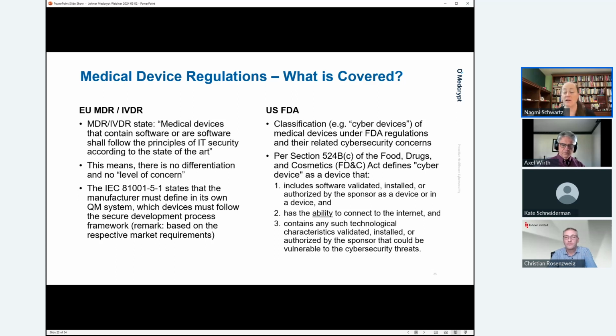You include software, you have the ability to connect to the internet, not necessarily the intention to do so, and you contain technology characteristics that are validated, installed, or authorized that could be vulnerable to a cybersecurity threat. Quite frankly, I perceive any software that's installed on a device to be potentially vulnerable, so I think 1 and 3 are a little bit redundant, but these are ANDed. A cyber device is only something for which all three of these characteristics are true. In the guidance, these three characteristics are ORed. The guidance is a set of recommendations, which FDA is holding people to pretty strictly, but that's a little bit different in terms of whether or not you can push back on FDA. If you have a cyber device, there is no pushing back. You have a legal requirement to provide cybersecurity documentation.